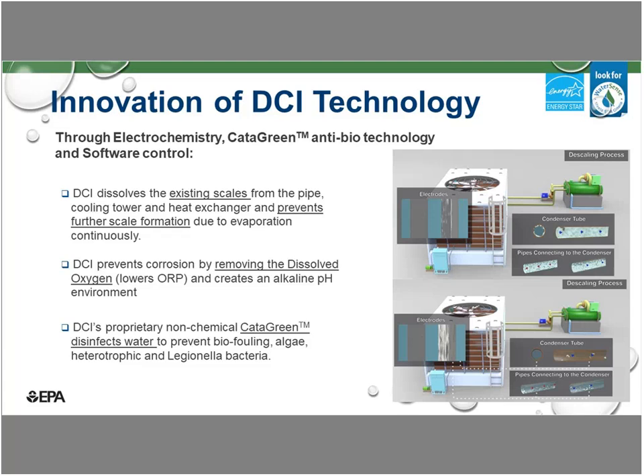So here, the water going back to the cooling tower is very low in minerals, scaling minerals. Because of that, existing scale in the system will start to dissolve. Of course, it will take time because our system dissolves them molecule by molecule. So it takes time, but eventually we will clean it up. The other part of it is that for cooling tower, the concern is corrosion.